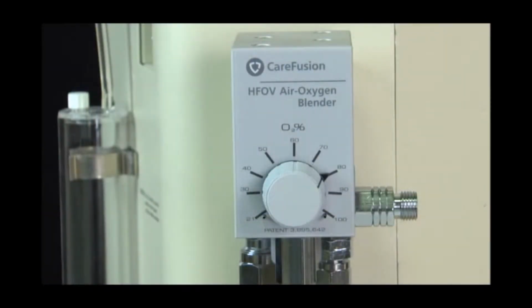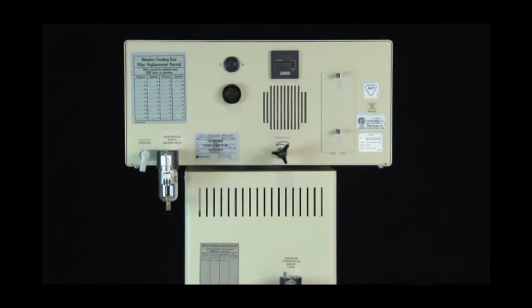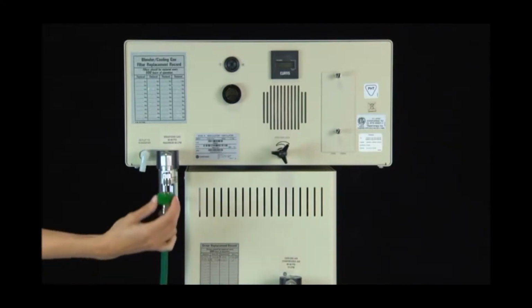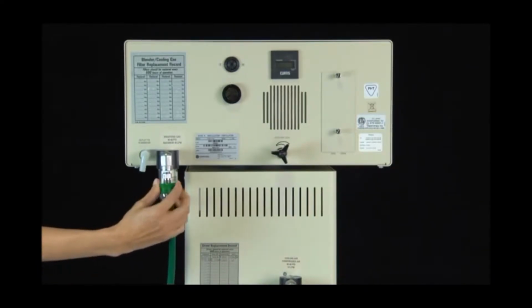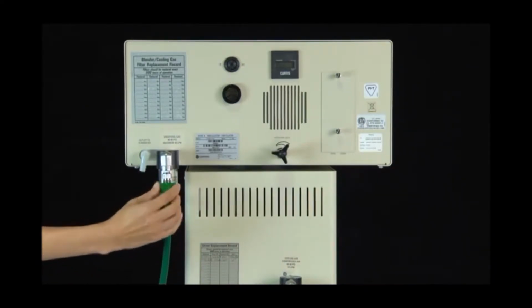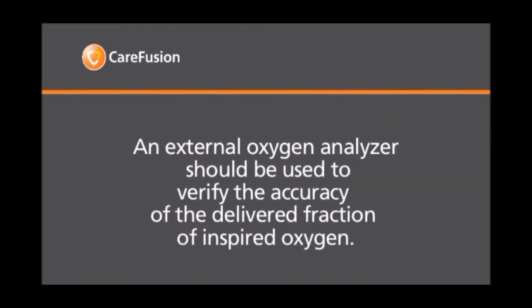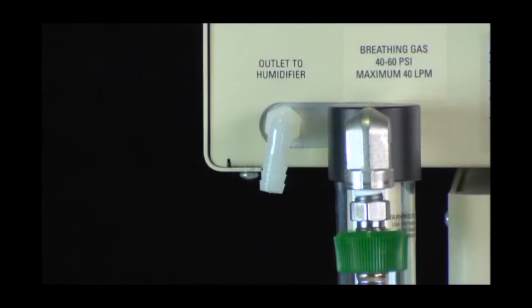An external blender must be used with the 3100A oscillator. The DISS connection for blended gases is labeled breathing gas. This fitting accepts a 50 psi input from the external blender. An external oxygen analyzer should be used to verify the accuracy of the delivered fraction of the inspired oxygen. The connector labeled outlet to humidifier provides patient breathing gas to the inlet of an external humidifier.